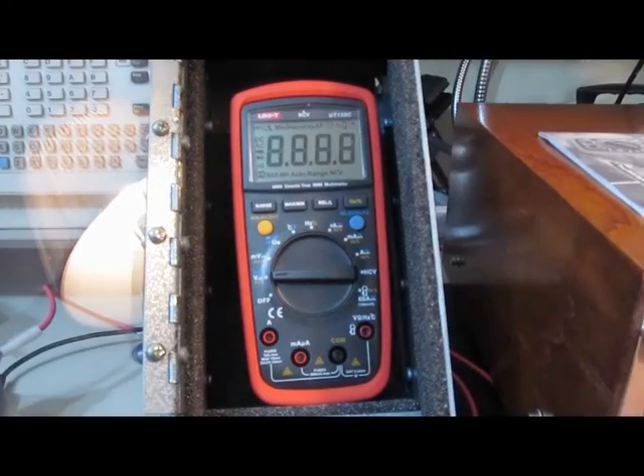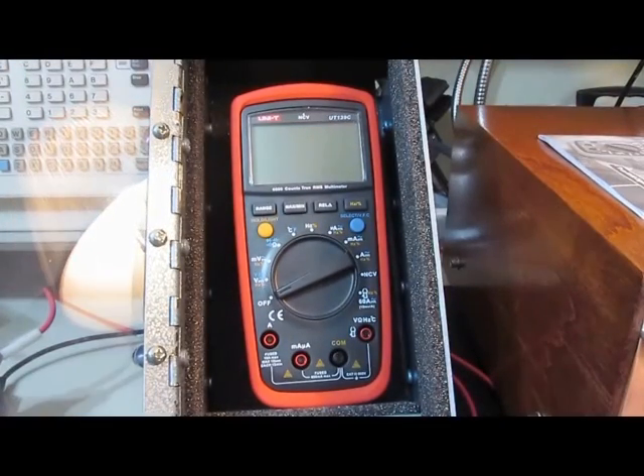Okay, it looks good. So it survived the AC plus DC test. So it's cleared the first three tests. That's the ESD, the high voltage DC, and the rectified AC test. So that's pretty good. That's on par with the UT90A. It's also on par with a lot of other meters. The surge testing is next. And I'm going to just start that out low, and we'll just start sweeping it up and see what happens.